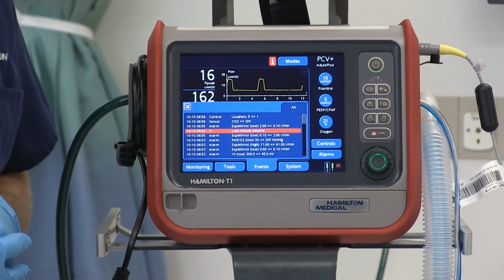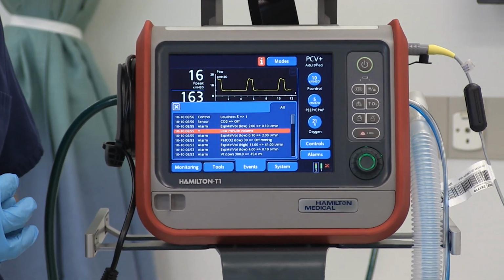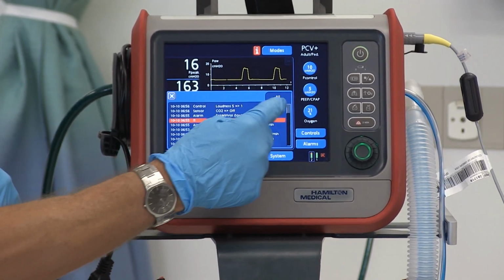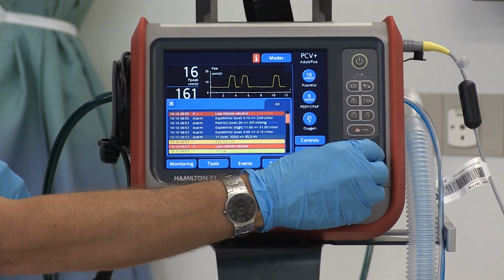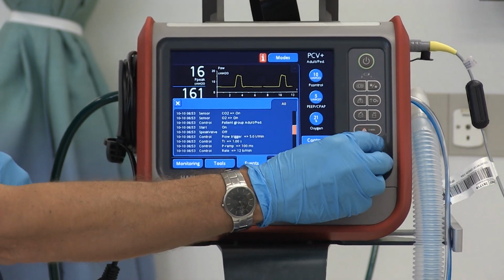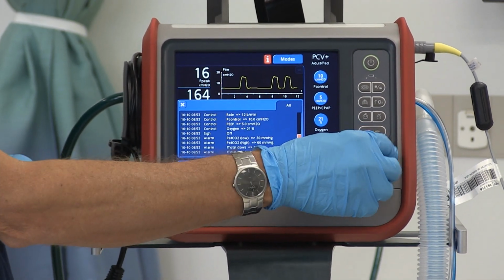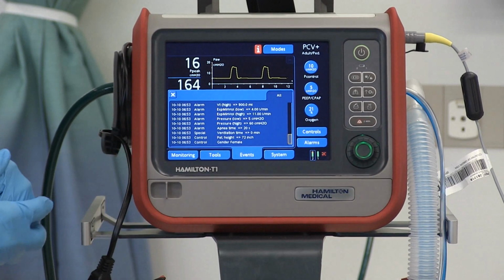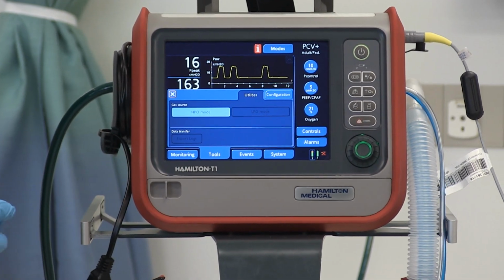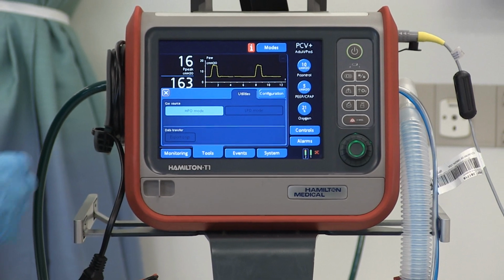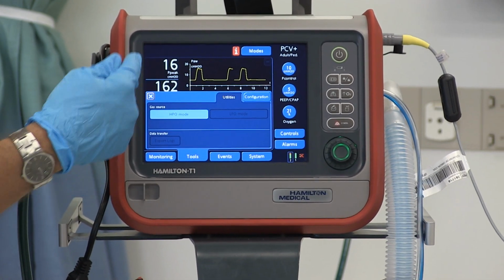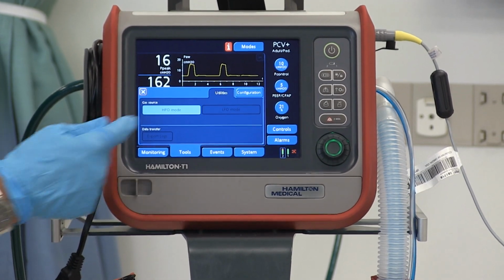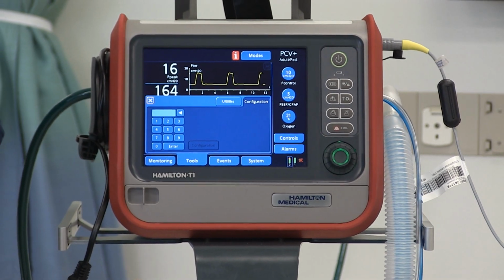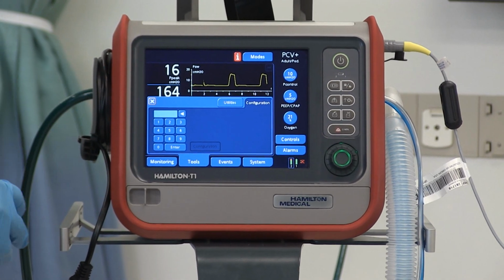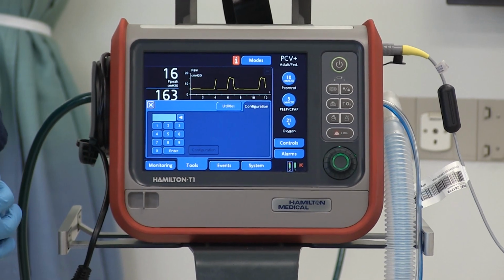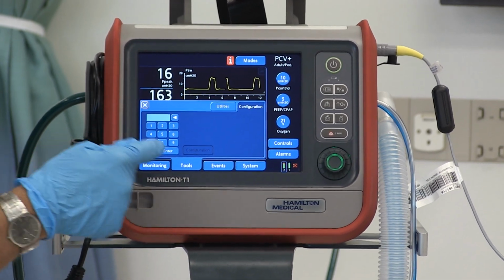Next tab over is your event log. So it's going to save the last 1,000 events available to you. To scroll back, it's in chronological order. Just activate the scroll bar, turn the knob, and you can go back. You can see all the ventilator changes and recent alarms up to 1,000 events. Again, and then here's the Tools tab. This is where you'd configure the ventilator from HPO or high pressure oxygen, or LPO for low pressure oxygen, or you can reach the configuration menu to adjust the graphics or monitor parameters that are displayed, things like that.